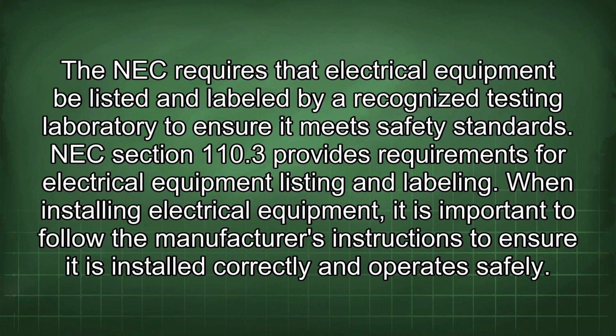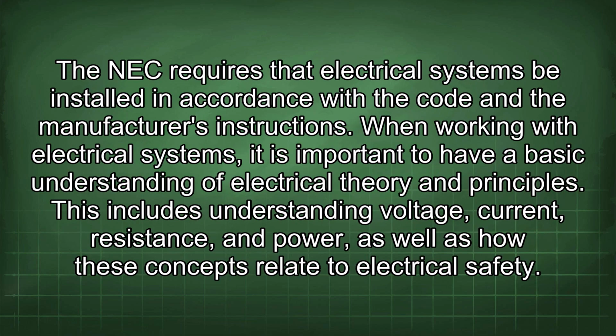The NEC requires that electrical equipment be listed and labeled by a recognized testing laboratory to ensure it meets safety standards. NEC Section 110.3 provides requirements for electrical equipment listing and labeling. When installing electrical equipment, it is important to follow the manufacturer's instructions to ensure it is installed correctly and operates safely. The NEC requires that electrical systems be installed in accordance with the code and the manufacturer's instructions.